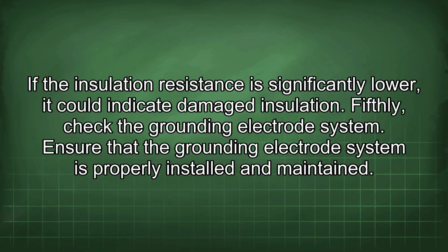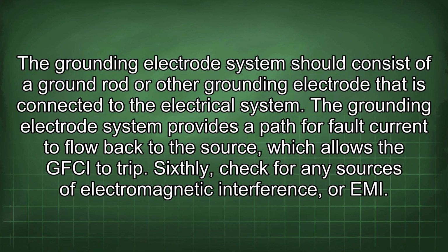Fifthly, check the grounding electrode system. Ensure that the grounding electrode system is properly installed and maintained. The grounding electrode system should consist of a ground rod or other grounding electrode that is connected to the electrical system. The grounding electrode system provides a path for fault current to flow back to the source, which allows the GFCI to trip. Sixthly, check for any sources of electromagnetic interference, or EMI.